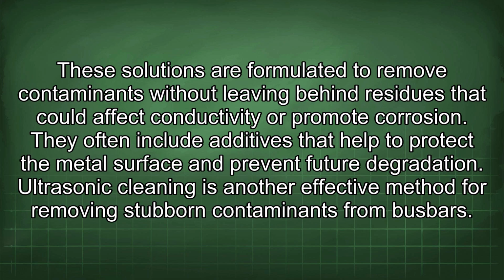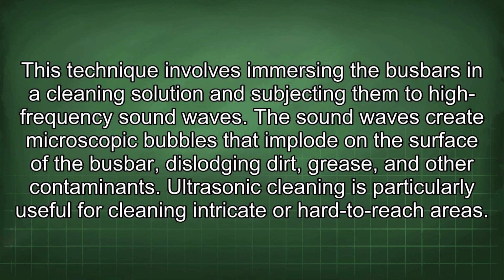Ultrasonic cleaning is another effective method for removing stubborn contaminants from busbars. This technique involves immersing the busbars in a cleaning solution and subjecting them to high-frequency sound waves. The sound waves create microscopic bubbles that implode on the surface of the busbar, dislodging dirt, grease, and other contaminants. Ultrasonic cleaning is particularly useful for cleaning intricate or hard-to-reach areas.